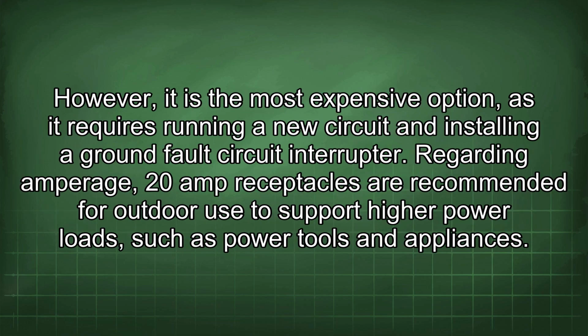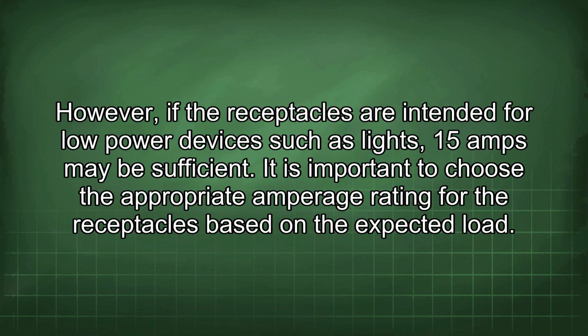However, it is the most expensive option, as it requires running a new circuit and installing a ground fault circuit interrupter. Regarding amperage, 20 amp receptacles are recommended for outdoor use to support higher power loads, such as power tools and appliances. However, if the receptacles are intended for low power devices such as lights, 15 amps may be sufficient. It is important to choose the appropriate amperage rating for the receptacles based on the expected load.